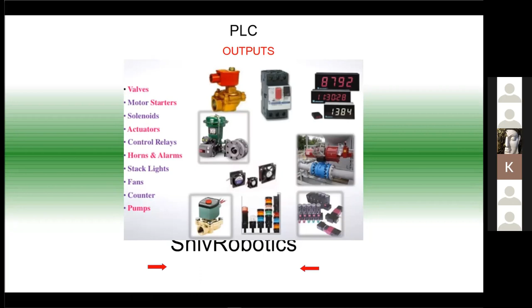So how is the PLC executing all these things? First thing is that we write a program for our logic, put it into the PLC, and ask the PLC to start executing it. When you say start executing, from the PLC point of view, 99% of PLCs will go with a self-test first. It has its own check for hardware or firmware failures. If that is passed, the PLC will say that I am ready. Once the hardware and firmware self-test is over, it starts scanning all the inputs.